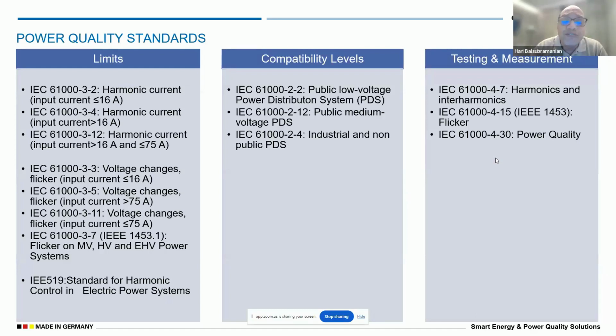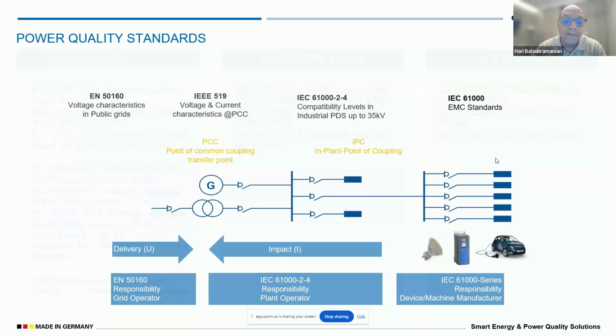There are quite a lot of standards which are already developed in IEC. It has already developed a standard for measurement. There are also compatibility levels for equipment, set as IEC standards. Say, for example, the incoming level or the voltage characteristics in the public grid or in the distribution network is characterized by EN 50160, or IS 17036, I think, for Indian standards, which is the characteristics of the voltage.